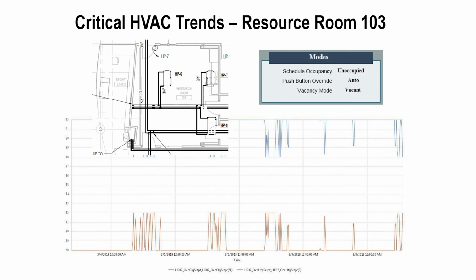There is one room in this building, in the center, just off the lobby. It's not exactly a storage closet, but kind of like one. They hold meetings in there now and then, and we wanted to pay particular attention to that room. We didn't want it to run on an occupied schedule like every other room in the building - we actually wanted it to be unoccupied 24/7.